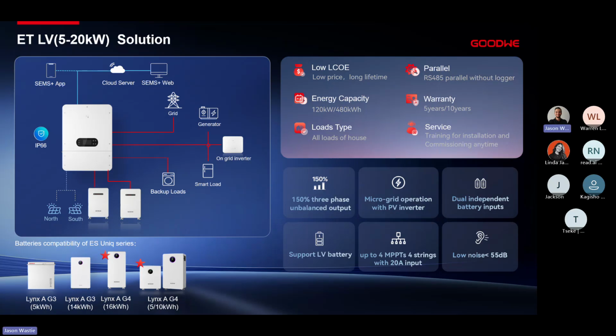Next is the 150% three-phase unbalanced output. In the residential space, it's extremely difficult to balance your loads in a three-phase application. We understand this, and due to that, we can run up to 150% unbalanced during off-grid application or towards our loads. Obviously, when the grid is there, we'll be able to supplement anything. However, when we're running off-grid from our batteries and PV, we can have up to 150% unbalanced output.